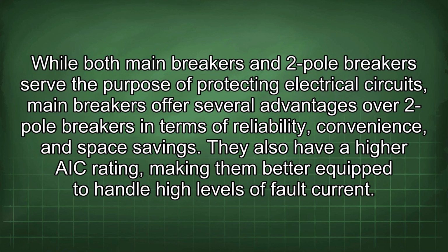While both main breakers and two-pole breakers serve the purpose of protecting electrical circuits, main breakers offer several advantages over two-pole breakers in terms of reliability, convenience, and space savings. They also have a higher AIC rating, making them better equipped to handle high levels of fault current.